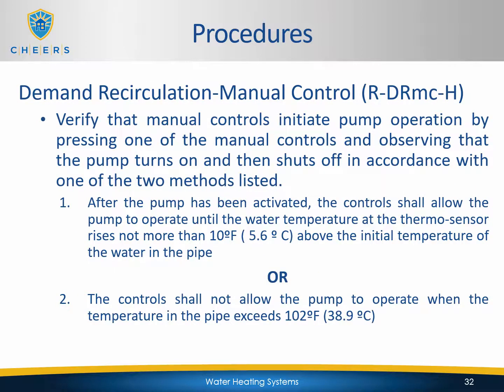You also need to verify that manual controls initiate pump operation by pressing one of the manual controls and observing that the pump turns on and then shuts off in accordance with one of the two methods listed. After the pump has been activated, the control shall allow the pump to operate until the water temperature at the thermosensor rises not more than 10 Fahrenheit, 5.6 degrees Celsius, above the initial temperature of the water in the pipe, or the control shall not allow the pump to operate when the temperature of the pipe exceeds 102 Fahrenheit or 38.9 degrees Celsius.